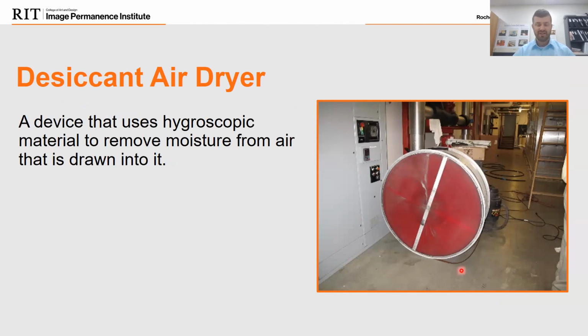I'll give an example of how this operates in a little bit, but wanted to include it because it is a component that you may see in an air handling unit. And those of you who have a desiccant and wondered what the wheel looks like, I wanted to include this picture. This is a very large version, about 4 feet, of what that wheel will look like, and that's inside your unit actually removing that moisture.